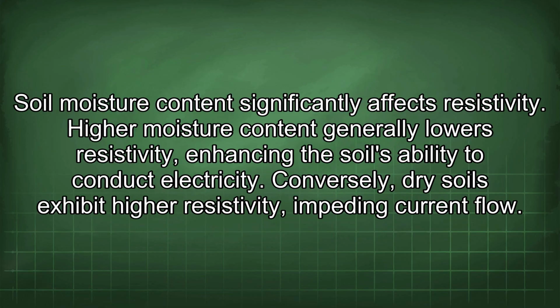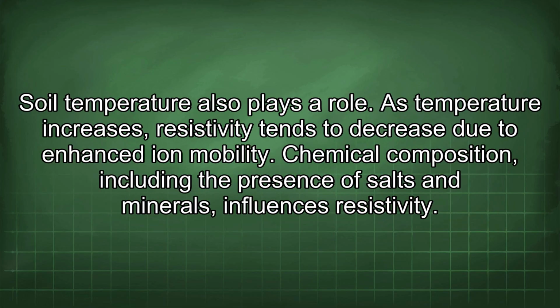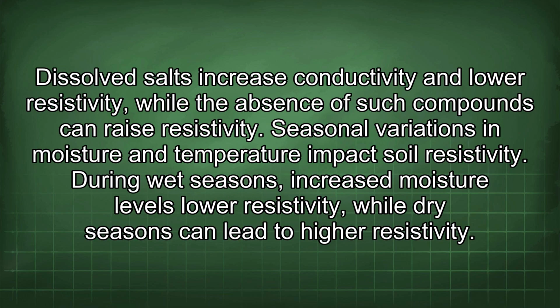Soil moisture content significantly affects resistivity. High moisture content generally lowers resistivity, enhancing the soil's ability to conduct electricity. Conversely, dry soils exhibit higher resistivity, impeding current flow. Soil temperature also plays a role. As temperature increases, resistivity tends to decrease due to enhanced ion mobility. Chemical composition, including the presence of salts and minerals, influences resistivity. Dissolved salts increase conductivity and lower resistivity, while the absence of such compounds can raise resistivity.